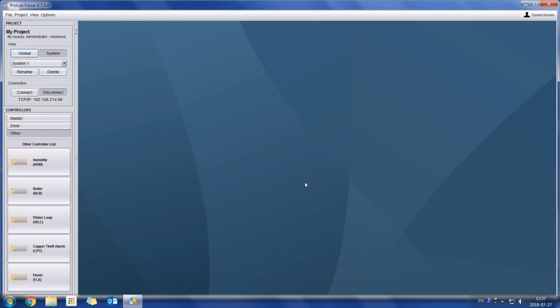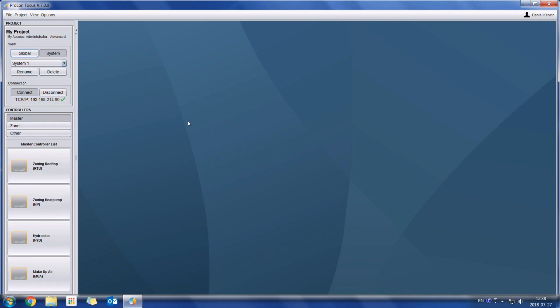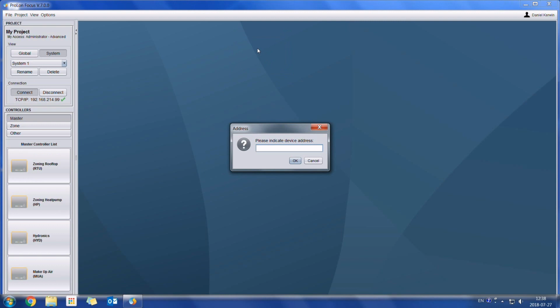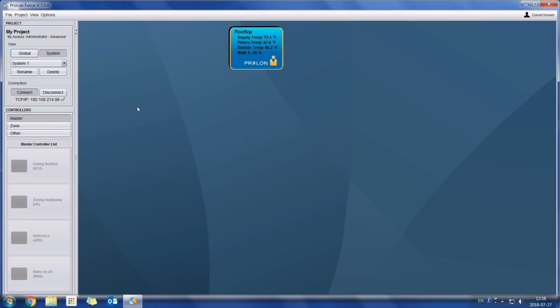Okay. So if I want to actually connect onto the controller, I have to press on the Connect button. So when I do that, I have a little green check mark which confirms that I am currently connected onto the controller. So on our system here, I know that we have a rooftop, so I'm simply going to go on to the master controller segment, and I'm just going to drag and drop it into our space here, and it's going to ask me for an address. So I know that this rooftop has an address number 10. Put number 10, and it pops up.